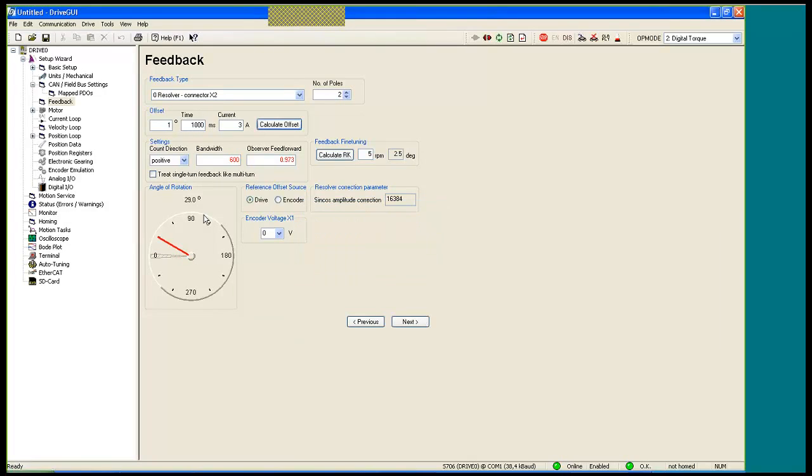Okay, here we go. It performs the set. So it's setting the offset value to 1, and it is repositioning the dial. There are multiple points in which this will show you 0, but it is working, and we're getting a 0 offset, or very close to 0, with the M phase.